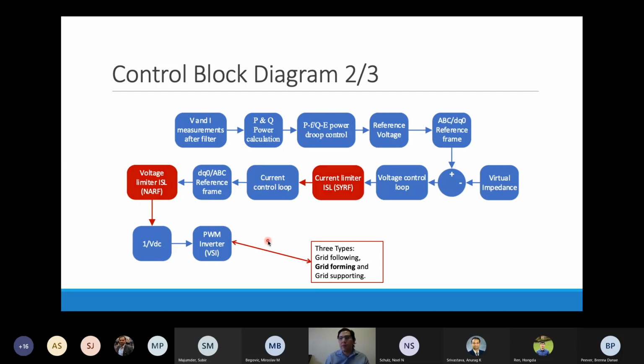Here, we know there are three main types of inverters: grid forming, grid following, and grid supporting. The one we utilize is built as a grid forming type of inverter, because we need to control it as an autonomous grid, able to control the voltage and the frequency by itself when it's not connected to the microgrid.